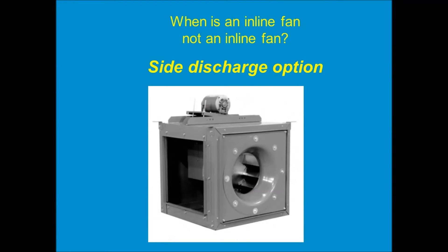This side discharge option is really handy in cramped mechanical rooms. A lot of times we see an inline fan installed right next to an elbow, which is a very poor inlet or discharge condition and causes a lot of unwanted turbulence. So instead of having a fan and then an elbow, let's just have the fan be the elbow — put the fan in the corner with the side discharge option, and the fan turns the air 90 degrees very efficiently with no loss of performance. Keep that in mind in a cramped mechanical room or plenum area.